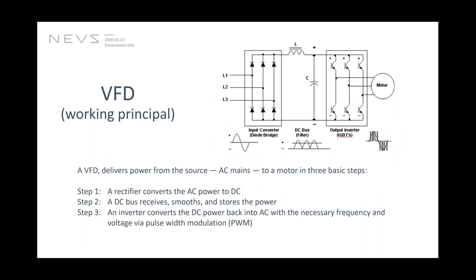The next step is the VFD, variable frequency drive application. What is the working principle of a VFD? Basically, a VFD transfers the power from the mains, meaning utility grid, to the motor in three steps. First, it rectifies the AC power from the grid to DC. And step two is the DC bus bar will smooth it out. I wouldn't say it's stored, but yeah, receive it, smooth it out, and then make it available as an input for the third phase, which is the inverter, which inverts the DC to AC by fast switching IGBTs, or it might be other gates, yeah, other switches.